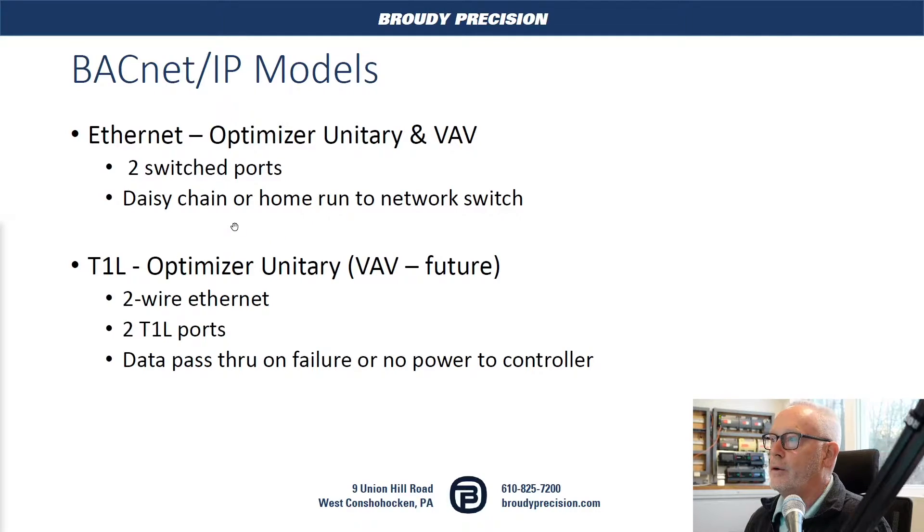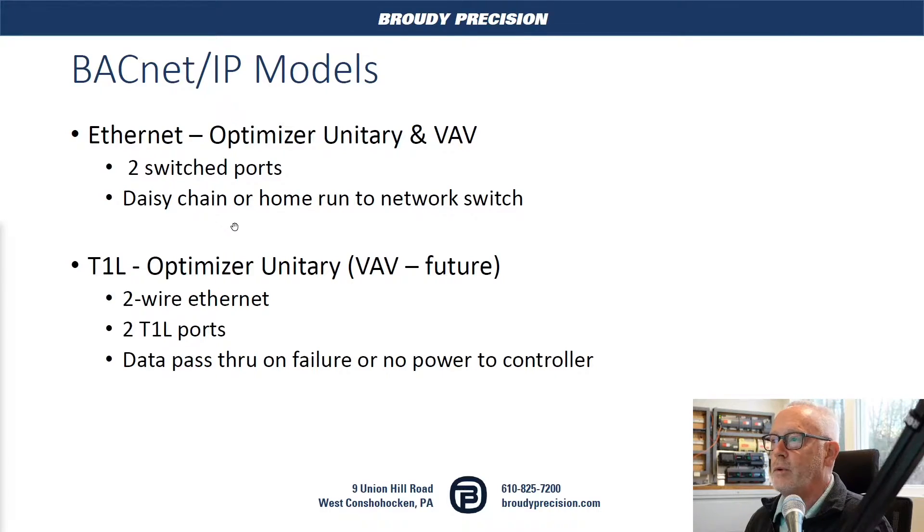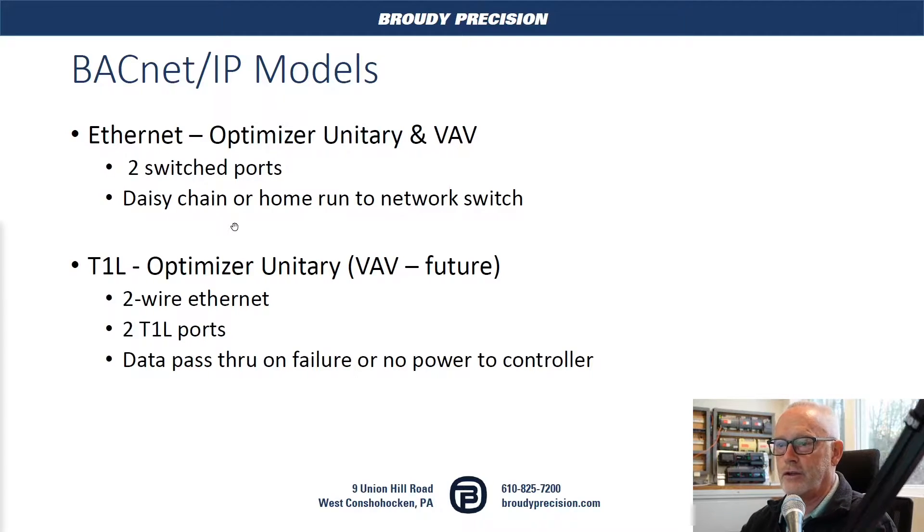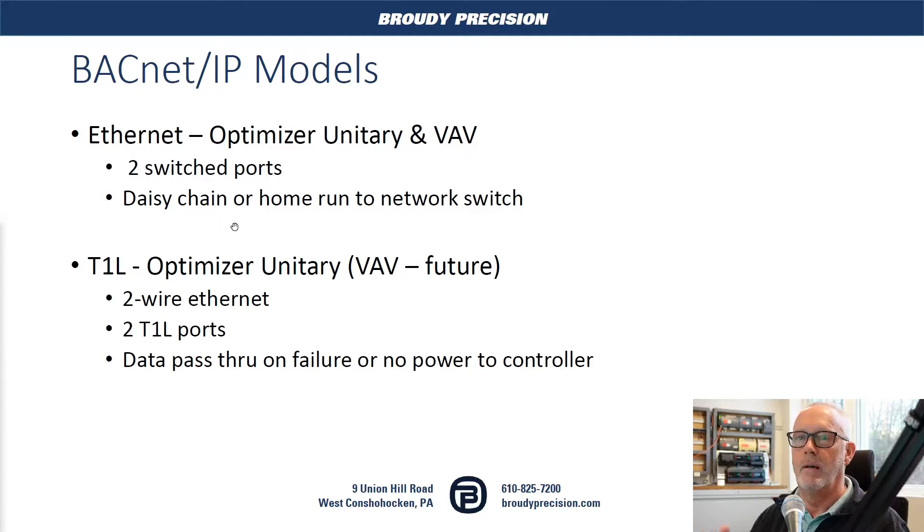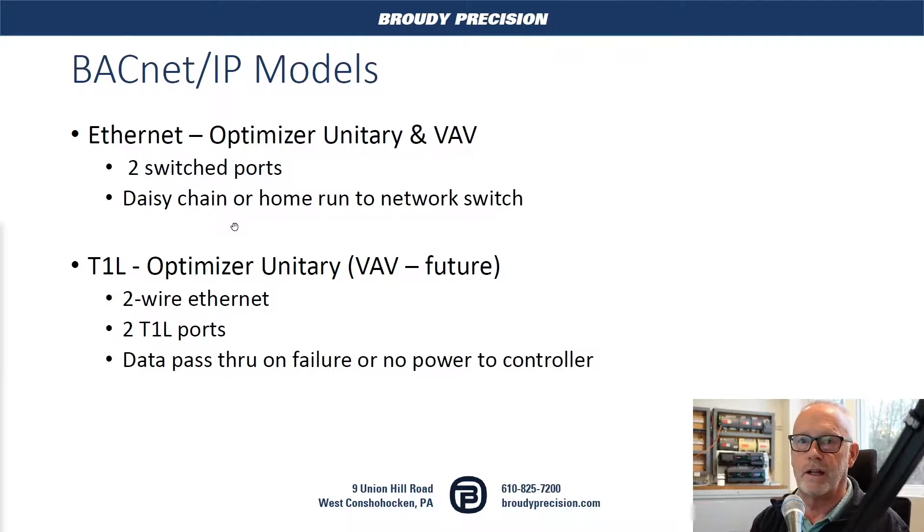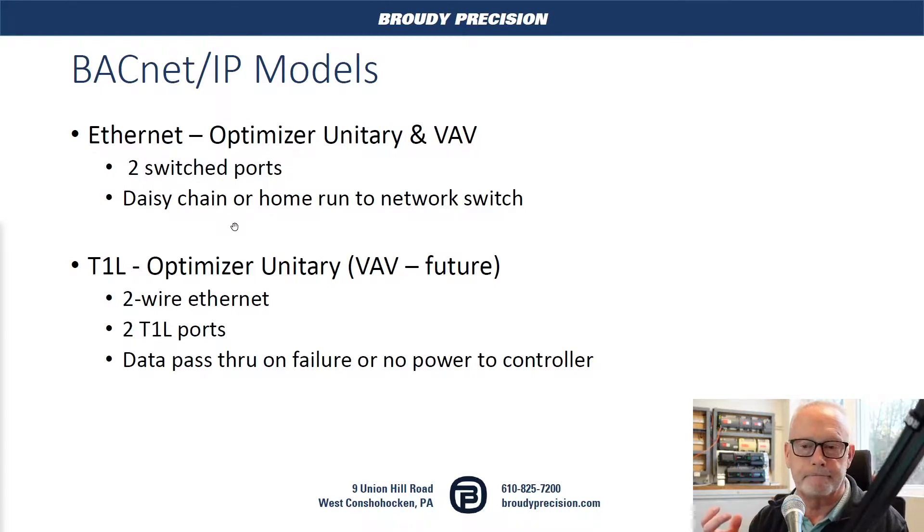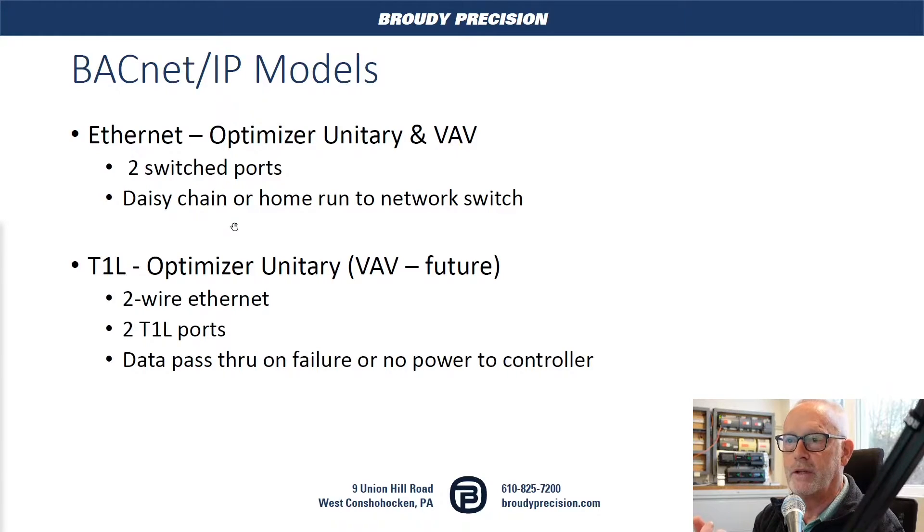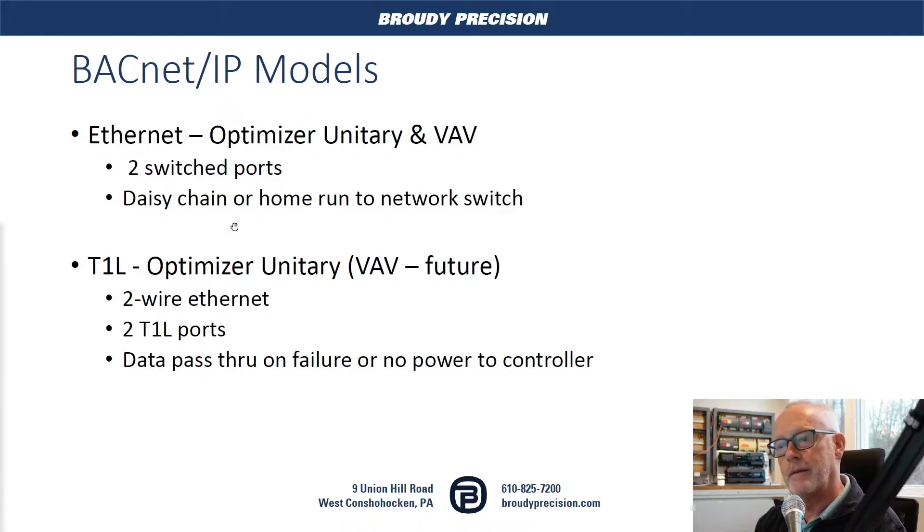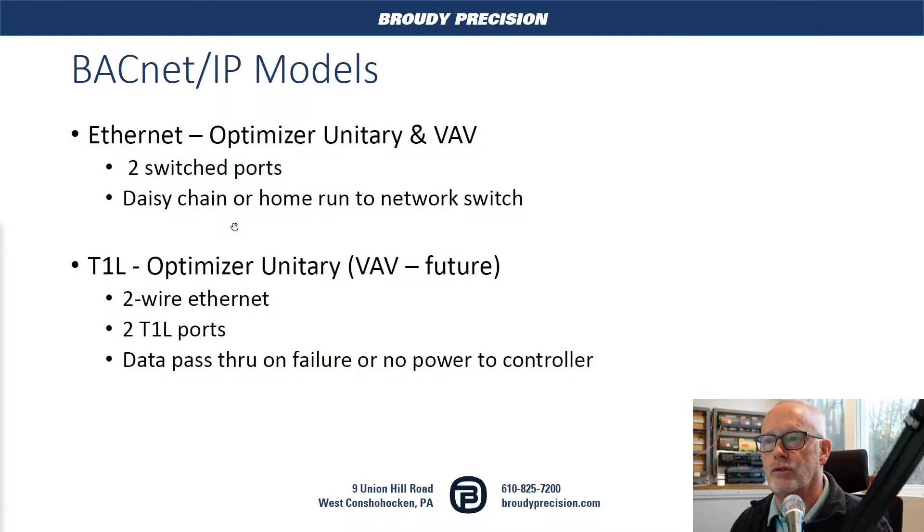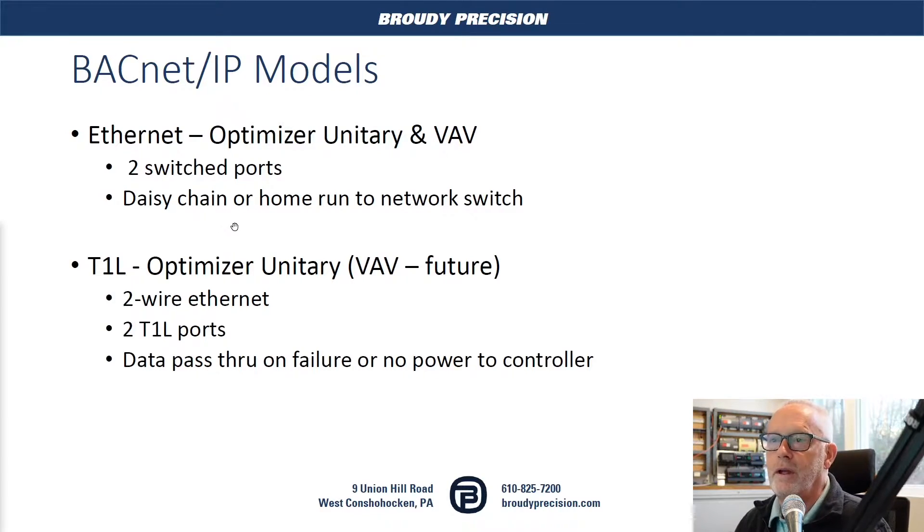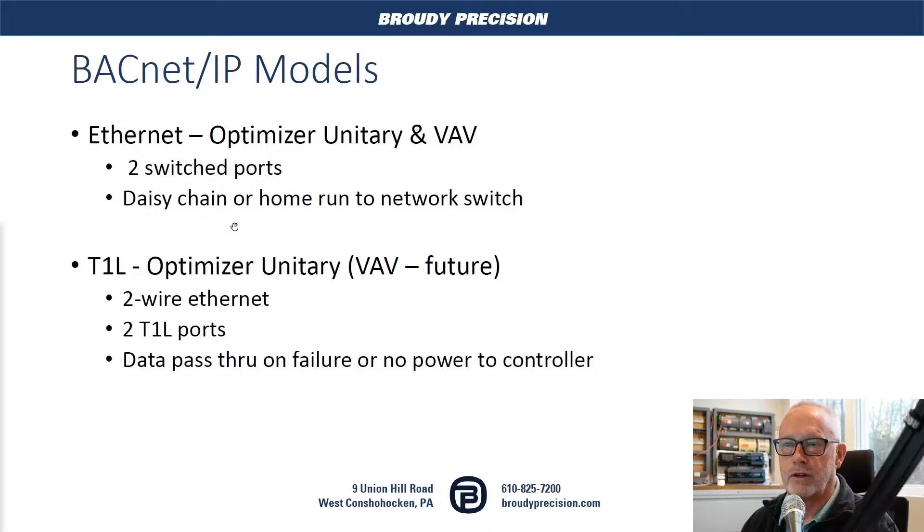The other is something newer that came out with the Optimizer Unitary and VAV in the future: T1L, which is a two-wire Ethernet. So think of the controller just like a standard BACnet IP controller, but the media is communications across a pair of wires, not a standard Ethernet patch cable. Each controller has two T1L ports on it, terminal strips. And when there's no power or the controller fails, it passes the data through. So when you daisy chain a T1L controller and you have one in the chain that fails or the power is removed, communication will still occur through the rest of the controllers.